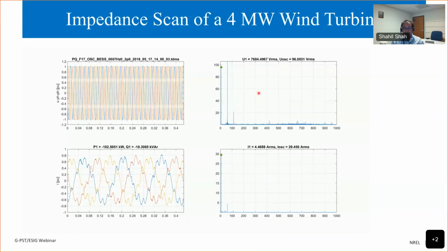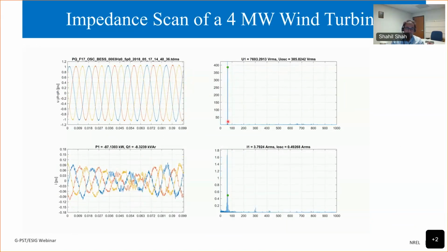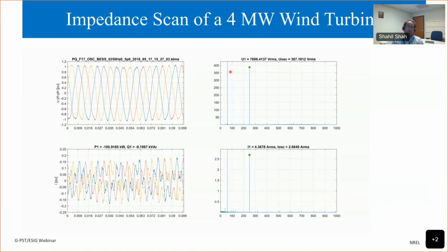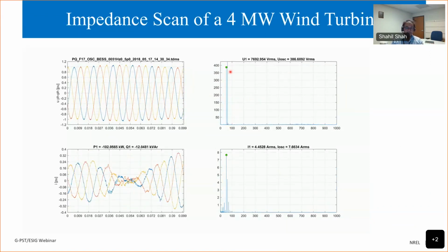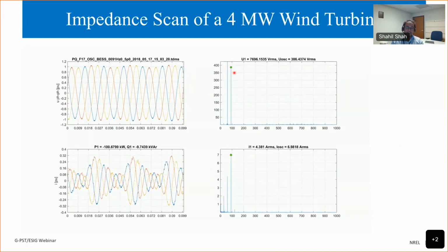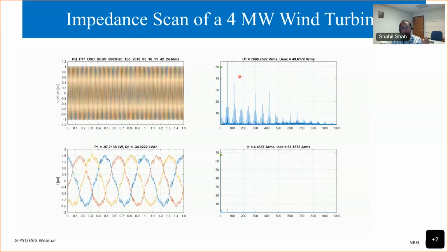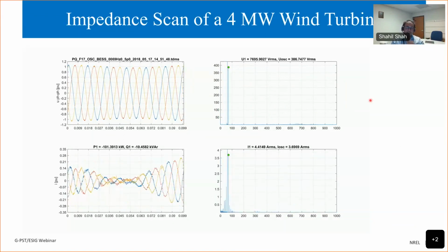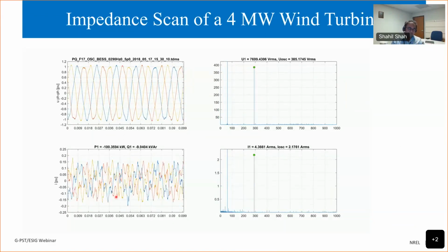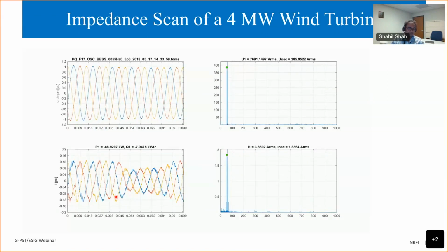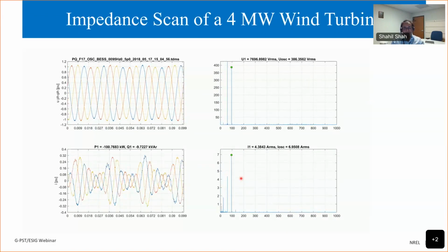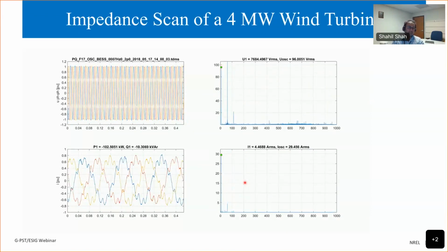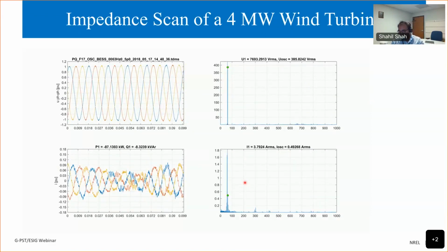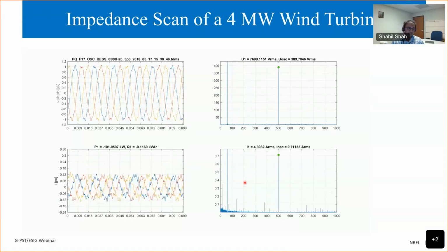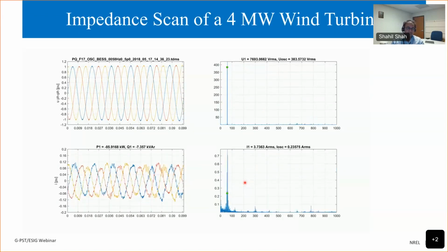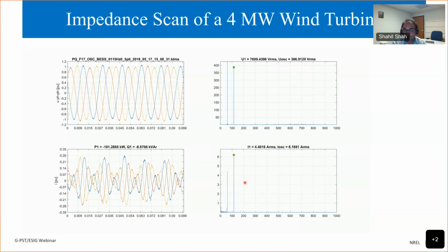The top right is basically the frequency spectrum. So as you can see, the fundamental frequency line stays constant. We are not changing the fundamental frequency component. And on top of that, the grid simulator adds this small few percentage of perturbation and changes the frequency. The bottom left is the output current from the turbine for different perturbations, and bottom right is the spectrum of current. So this is how we scan the impedance response, either using this impedance measurement system or the software tool that I just described.